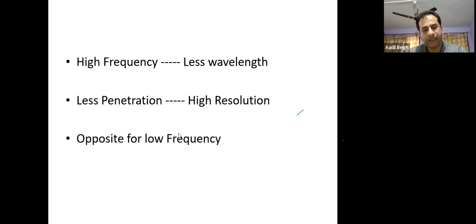Opposite for the low frequency: the curvilinear probe for ultrasound, because we need more penetration. Low frequency probes are, for example, 2, 3, 4 megahertz. So we use 2, 3, 4 megahertz for more penetration, because they have more wavelength, more penetration. But with the penetration, the image quality and resolution is less.